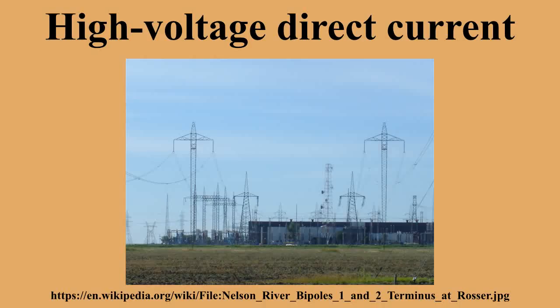The combined economic and technical benefits of HVDC transmission can make it a suitable choice for connecting electricity sources that are located far away from the main users. Specific applications where HVDC transmission technology provides benefits include undersea cables transmission schemes, endpoint-to-endpoint long-haul bulk power transmission without intermediate taps, usually to connect a remote generating plant to the main grid. For example, the Nelson River DC transmission system in Canada. Another is increasing the capacity of an existing power grid in situations where additional wires are difficult or expensive to install.